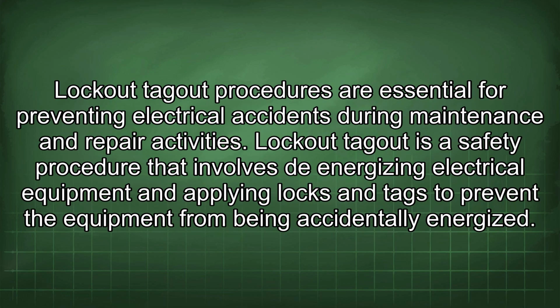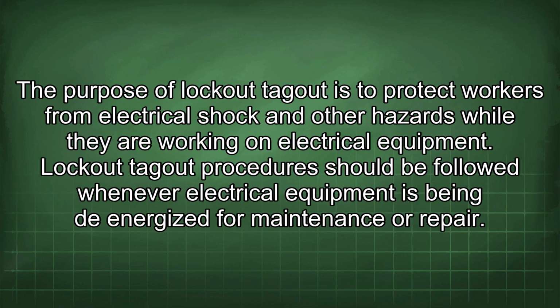Lockout-tagout procedures are essential for preventing electrical accidents during maintenance and repair activities. Lockout-tagout is a safety procedure that involves de-energizing electrical equipment and applying locks and tags to prevent the equipment from being accidentally energized. The purpose of lockout-tagout is to protect workers from electrical shock and other hazards while they are working on electrical equipment. Lockout-tagout procedures should be followed whenever electrical equipment is being de-energized for maintenance or repair.